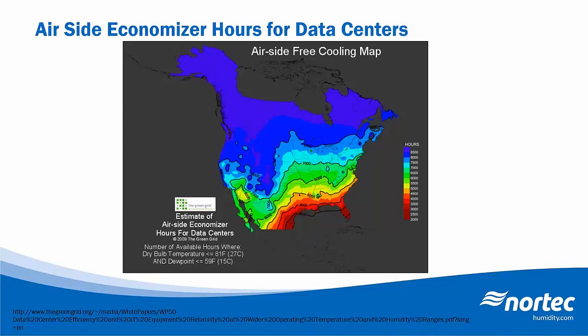So there's three main modes of operation for economization. The first is economization over a fairly narrow temperature range with little or no change in the temperature in the data center itself. In this case, if the outside air condition changes or the internal load changes such that economization cannot provide the desired conditions, typically a chiller system or a backup system will ramp up to provide additional cooling capacity.